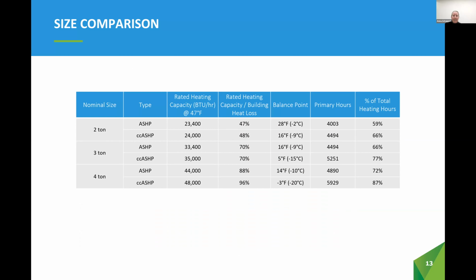While in all 6 cases, an air source heat pump does not meet the building's peak heating requirements on a peak design day, they still meet a significant portion of the heating season hours. Does that mean they don't work in Manitoba? No. Air source heat pumps do work for our climate in Manitoba, just additional considerations need to be made.